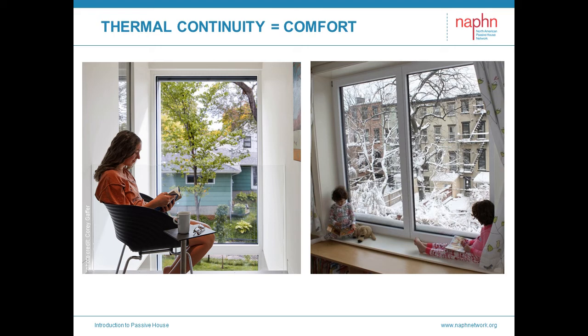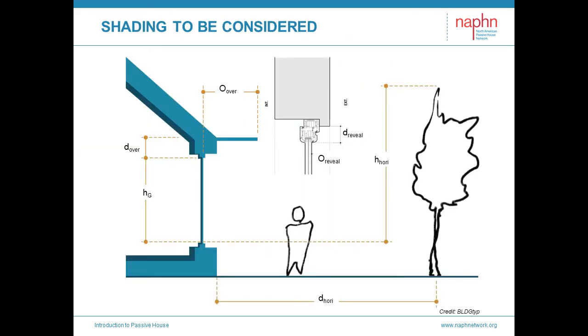High-performance windows disproportionately affect the overall energy balance performance of the building. They offer greater design freedom, flexibility, and more options — value that cannot be appreciated in an isolated budget line. While windows provide views, daylight, and useful passive heat gains, improperly designed windows can cause significant overheating, resulting in discomfort and additional air conditioning requirements. Overheating is a common problem in conventional buildings across the country today. The best approach is to carefully provide proper shading — by how the window sits in the wall, an architectural element, or landscaping. Exterior shading is most effective, and solar shading cannot be optional.